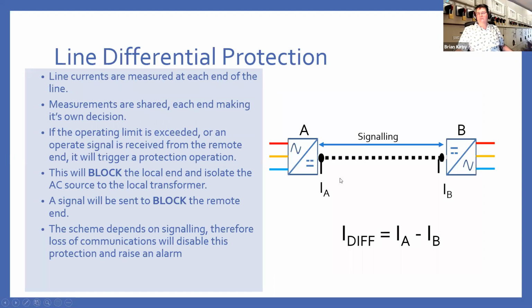Similarly with AC systems, because we have communications between the two ends, we can actually share the measurements at either end, and we can perform a differential. So if you have, say, 1000 amps being fed in at this end, and you're only seeing a few tens of amps coming out the other end, that suggests you've got a fault in your cable, and you can again perform a differential block locally, and you can send a remote block to the other end. Of course, anywhere you detect a fault in the cable, the likelihood is it's going to be a permanent fault, and some investigations will be required before you can re-energize the system.